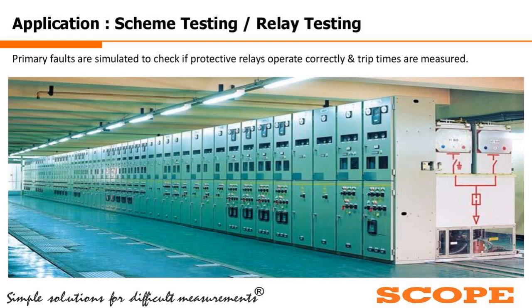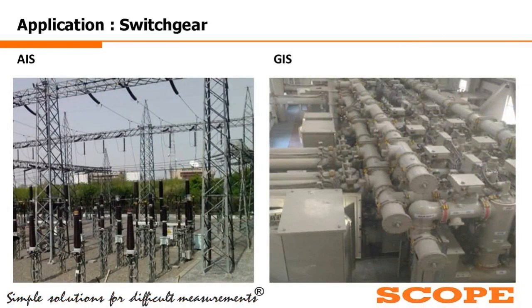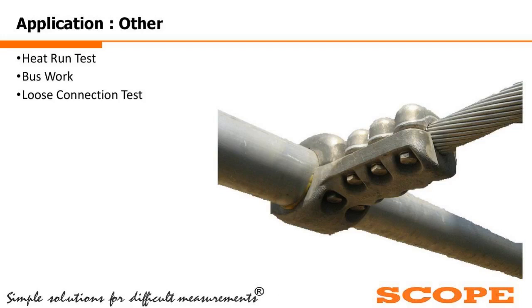Protection scheme or relay testing can also be done with the primary injection test. Rated current flows from the CT and accordingly when the current exceeds the limit, the relay senses it and gives the command to the circuit breaker. Checking the healthiness and correctness of the protection relay is very important, and this is easily done with primary current injection. Other applications include verifying the design of GIS (gas insulated switchgear) and AIS (air insulated switchgear).